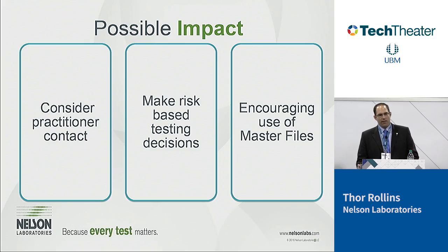A good example: we had a device just recently that was a face shield for a surgeon, okay? They submitted it without biocompatibility because it doesn't contact the patient. It's a face shield. But the FDA came back and said, we need to evaluate biocompatibility for the sweatband that the face shield has, because it contacts the forehead of the surgeon. So they contacted me and asked what they needed to do. We just had to do biocompatibility assessments on that material, because it contacts the practitioner and it's not covered by any kind of protective wear, right?